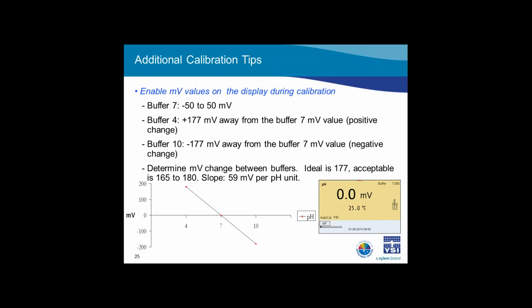Next, make sure you are looking at the pH millivolts during calibration. Again, the pH millivolt value is the raw signal coming from the sensor that the instrument converts into pH units. Evaluating the millivolt value during calibration can help us document sensor aging and help us to determine if the sensor needs serviced, cleaned, or replaced.